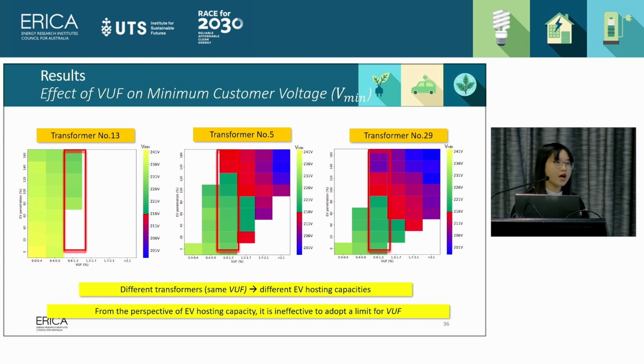Okay, so now let's compare different transformers. Here we select the same range of voltage imbalance factors, which is marked as a red box. We can see that for transformer number 13, there's no voltage issue, so the EV hosting capacity can go to 160%. However, for transformer number 5, the maximum EV penetration level for this voltage imbalance range is 120%, and for transformer number 29, the EV hosting capacity can only reach 80%.